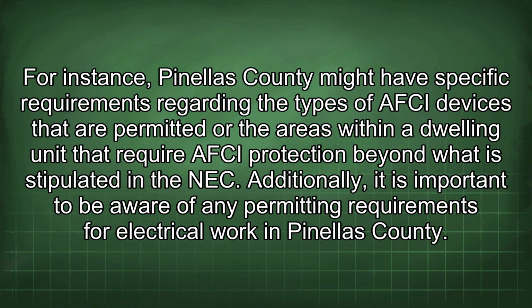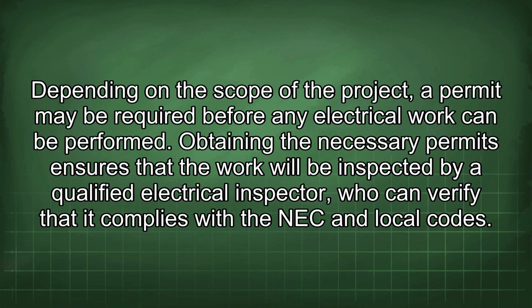For instance, Pinellas County might have specific requirements regarding the types of AFCI devices that are permitted or the areas within a dwelling unit that require AFCI protection beyond what is stipulated in the NEC. Additionally, it is important to be aware of any permitting requirements for electrical work in Pinellas County. Depending on the scope of the project, a permit may be required before any electrical work can be performed. Obtaining the necessary permits ensures that the work will be inspected by a qualified electrical inspector who can verify that it complies with the NEC and local codes.